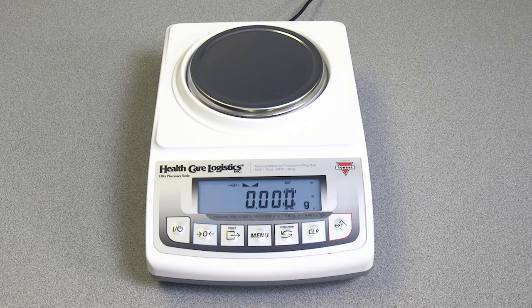Simply start by making sure there is nothing on the pan. Press the menu button and select Calibrate when it appears on the display by pressing T. When Start appears on the display, press T to select. If you do not see this option, you may have a scale that can be calibrated externally. The internal calibration will begin to run. As it is running, weight will appear on the display. When finished, the scale will return to weighing mode.